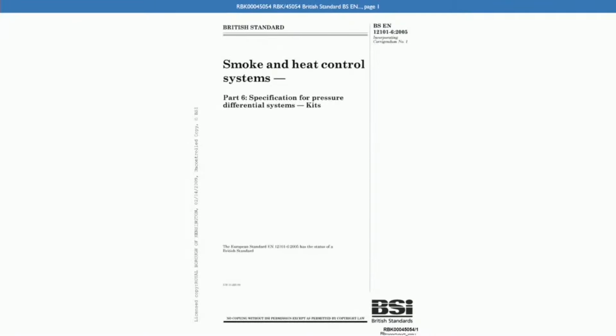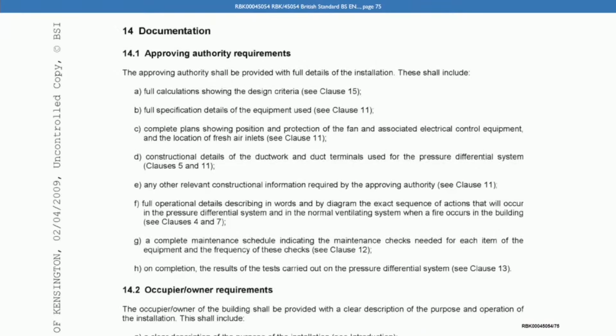Right. If we could go now to British Standard EN 12101 Part 6, we find this at RBK 3045054. There is that British Standard. And I think you agree from what you said earlier, but just to be clear, that even though the system wasn't designed to be in complete compliance with the systems identified in this British Standard, this does set out a methodology to test the criteria that you selected. Do you agree with that? Yeah.